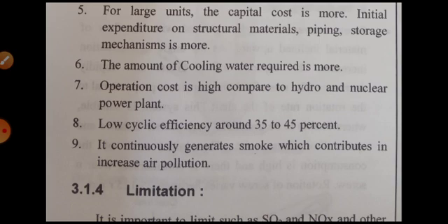You heat the steam, then you exhaust the steam into the turbine. There are also losses. The turbine is connected to a generator, and while generating there are also losses, and while transmitting, the transmission losses are also there. Therefore, calculating all these losses, if we calculate the total efficiency of the power plant, considering all the other efficiencies, we get only around 35 to 45% efficiency, which is very low compared to other power plants.